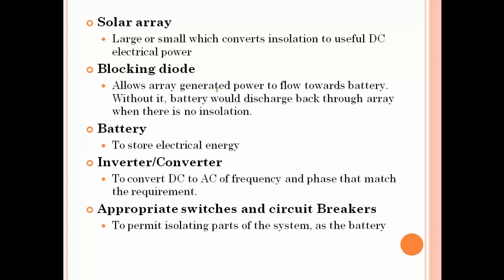The solar array generates electricity. The blocking diode prevents current from flowing in the reverse direction back to the array. The battery is used to store electrical energy. The inverter or converter is needed because solar arrays produce direct current (DC), and a DC-to-AC converter is used to supply AC power. Finally, appropriate switches and circuit breakers are included.